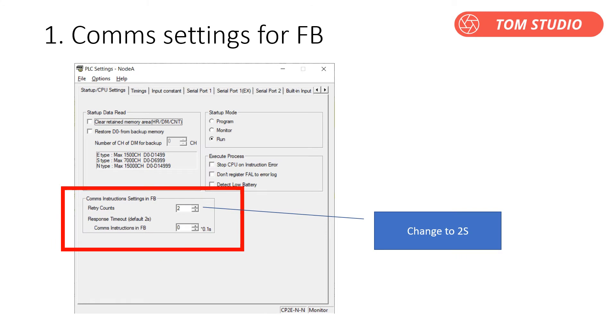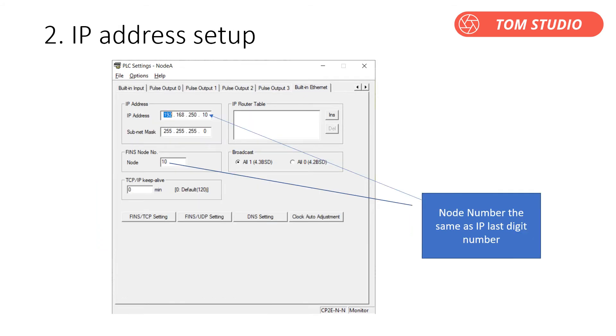It is necessary to change the PLC settings as shown. Change the response timeout to two seconds. This step is important: it is necessary to set the node address to the same value as the last digit of the IP address. As you may know, Omron FINS protocol uses three numbers — network number, node number, and unit number — to locate a device on the network. So this step sets up the FINS node address.